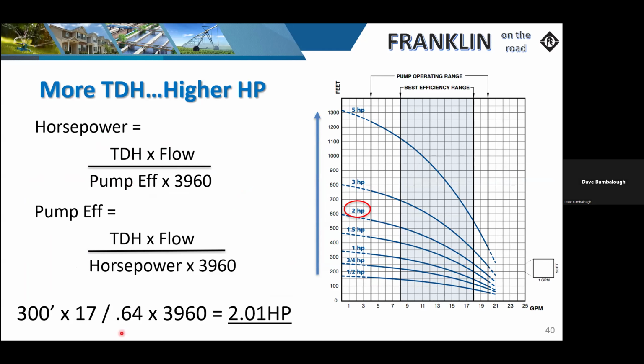As you can see, I've already reverse mathed this, and that particular pump is only 64% efficient. Okay, so not very good. It's not something we want to brag about. Hence the reason you don't see a pump efficiency curve up here. Usually they'll put one up here that shows where that pump efficiency is. But in this calculation, we're figuring 300 for TDH times 17 divided by the efficiency, and then the 3960 is basically a conversion. So it says that this is equal to about 2 horsepower.